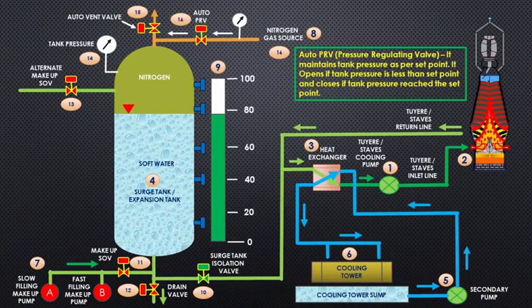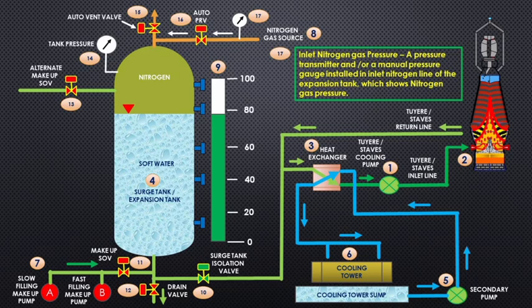Auto PRV (Pressure Regulating Valve) maintains tank pressure as per set point. It opens if tank pressure is less than set point and closes if tank pressure reaches the set point. Inlet nitrogen gas pressure: a pressure transmitter and/or manual pressure gauge installed in inlet nitrogen line of the expansion tank shows nitrogen gas pressure. Hope you understand. In case of any doubts, please mention in comments.